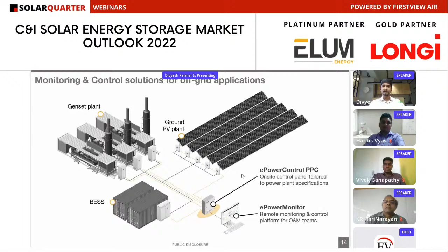So for the islanded operation, basically you have two options. Either you are running the battery storage as a primary source or genset as a primary source. So when it is about the greenfield projects, means very new projects where you have sufficiently large batteries to take care of your loads, in that case, batteries are normally forming the grid, and if the battery state of charge falls below a certain level, then the gensets will be coming into the picture as a backup purpose. So here the EMS control functions are the diesel off mode as well as the maximum solar penetration.